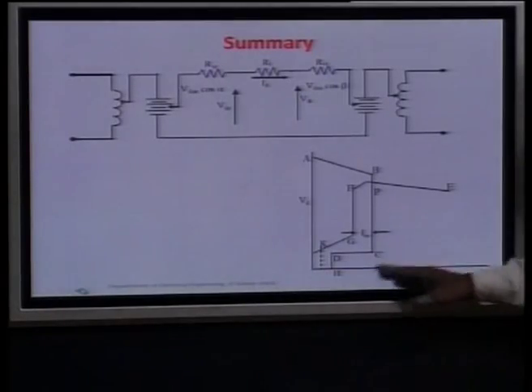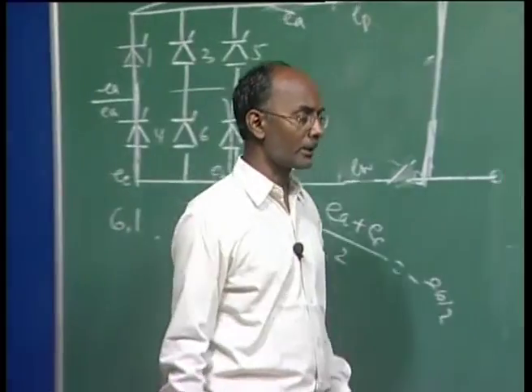This is called the VDCOL, that is the voltage dependent current order limiter characteristic, which is introduced especially during the lower side. The same is repeated if your converter becomes inverter and your inverter becomes rectifier. So, it will be repeated on the lower side.